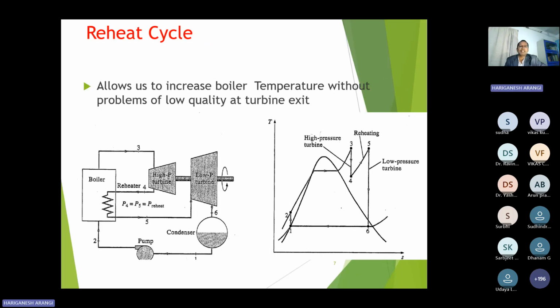The reheating cycle: the Rankine cycle, like a simple cycle, operates in low megawatt, low capacity power plants, whereas the reheat cycle improves the efficiency of the turbine and the power plant. There will be multiple cylinders, either double cylinder or 3 cylinders, like an HP turbine, IP turbine, and LP turbine. First, after the boiler, steam enters into the HP turbine. From the HP turbine, the steam comes back to the boiler, where it takes a reheating. Again, that reheated high temperature steam enters into the IP turbine. From the IP it goes to the LP turbine, and from the LP turbine it comes to the condenser. Again, the process remains the same. In this reheating cycle we get more efficiency.